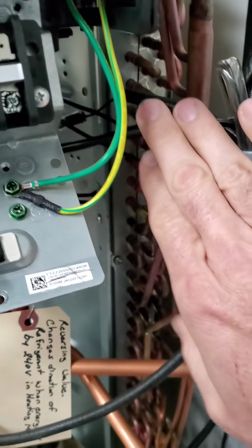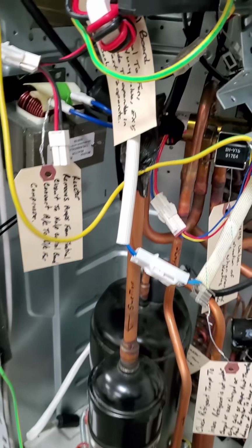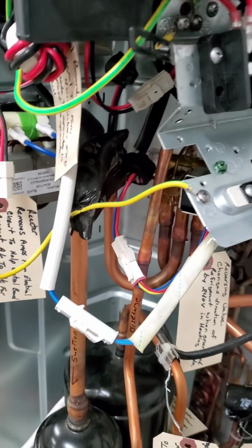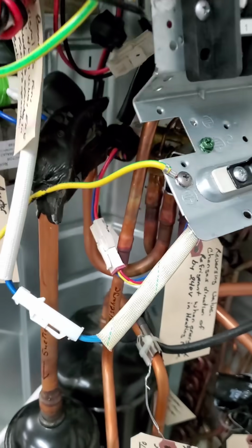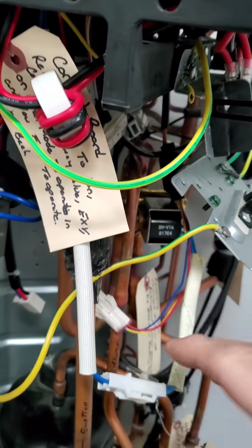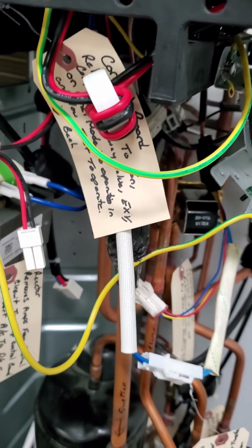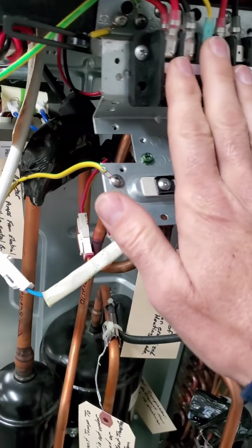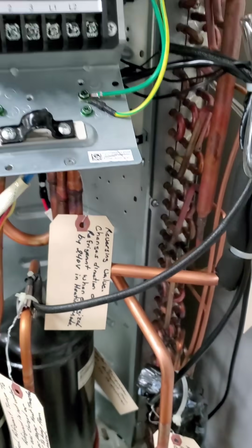One thing you can do, and you can test every sensor, and I have a video of that, but to keep this short, what you can do is, if you have an E1 code and you're questioning where the problem is, whether it's the control board, whether it's the wiring, whether it's a sensor, what you do is unplug the sensors. Just unplug them. You will throw a sensor code, but your E1 would go away. Because if it throws a sensor code, you know that the outdoor unit is now communicating with the indoor unit.